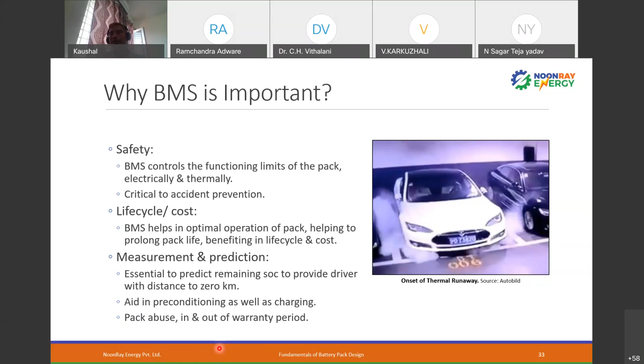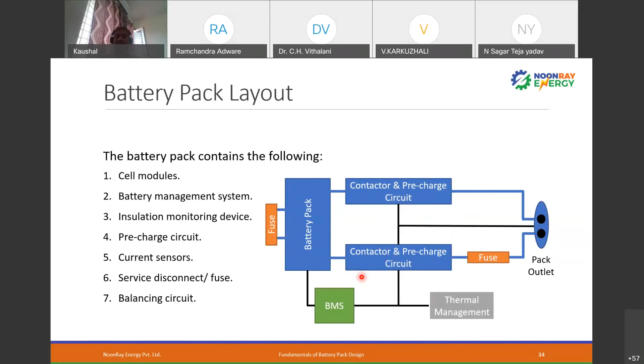Now, what does a battery pack contain? A battery pack contains a cell module, battery management system, insulation monitoring device, pre-charge circuit, current sensor, service disconnect fuse, balancing circuits, and all those things. And these are all here. These are all part of the inside of the battery pack only, except this pack outlet. Whatever we are showing you here is a part of the battery pack itself. So the fuse will go inside the battery pack, contactor and pre-charge circuit will go here. Contactors and pre-charge circuit again are positive and negative. There would be an additional fuse here. The BMS would be a part of it, and the thermal management system may or may not be a part of the battery system.